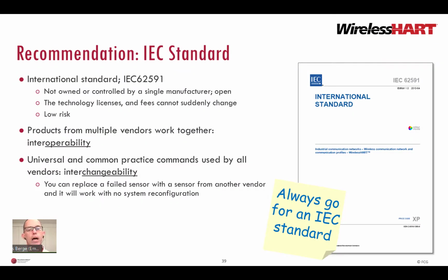WirelessHART is supported by multiple vendors. This means you can buy WirelessHART products from multiple vendors and they will work together, called interoperability. Over and above interoperability, WirelessHART has universal and common practice commands used by all vendors, meaning you can also replace a failed sensor with a sensor from another vendor and it will work without system reconfiguration, called interchangeability. Over and above this, WirelessHART is an international standard, so it's not controlled by a single vendor. So the technology, the licenses, and the fees cannot suddenly change.